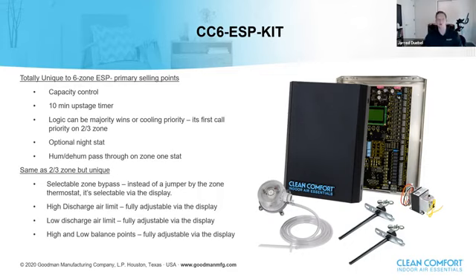However, when we get into commercial applications, you might have a volatile type zone like a server room where cooling needs to take priority. So we can actually switch it to cooling priority, just set on a dip switch there on the panel, so that if a cooling call comes in, we're going to make sure we satisfy that before we go to any heating calls.